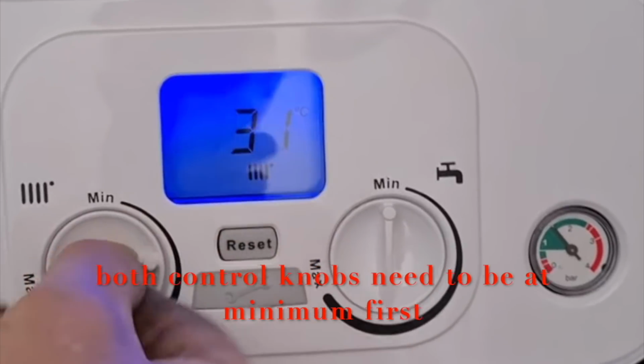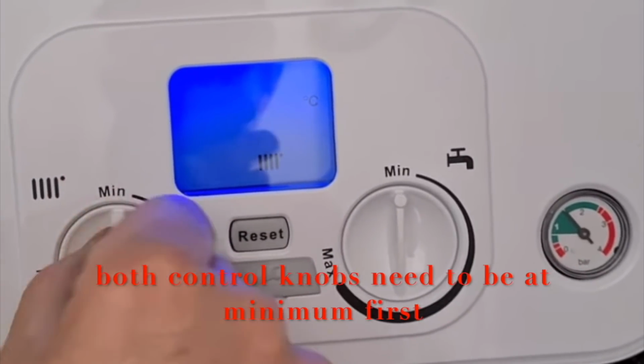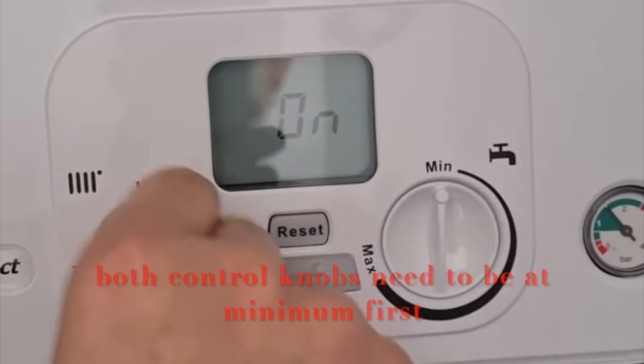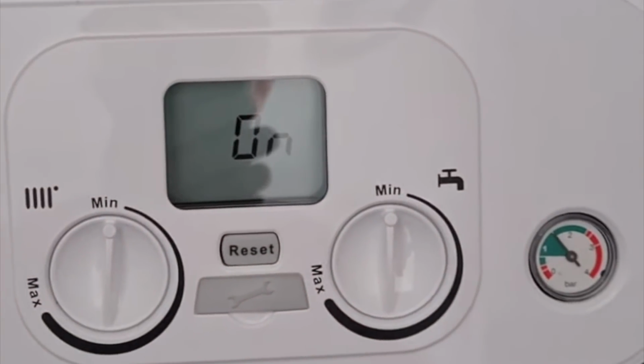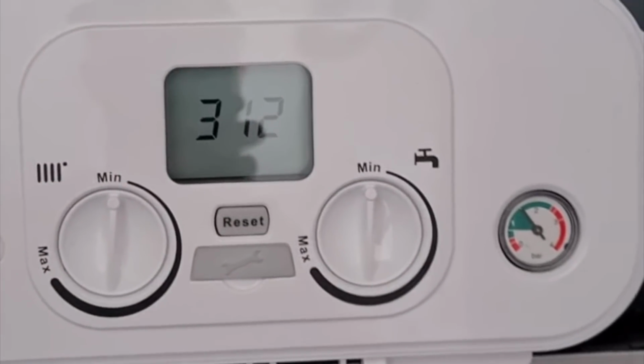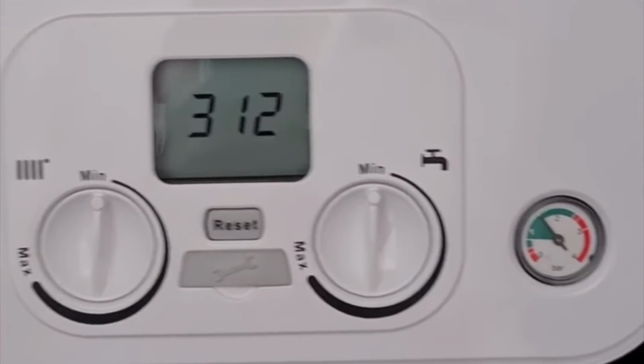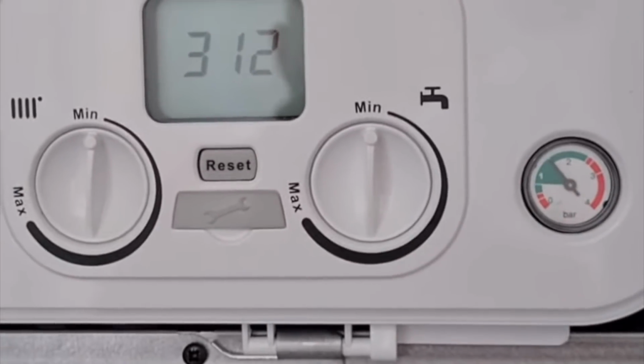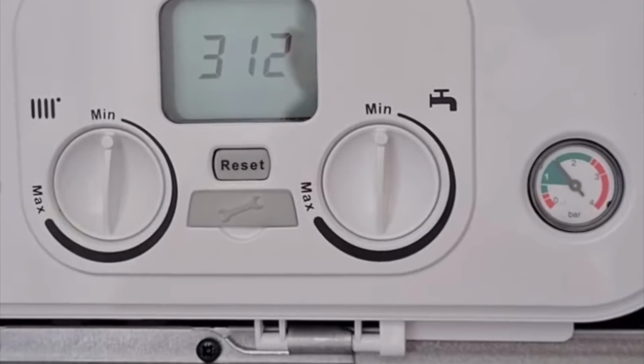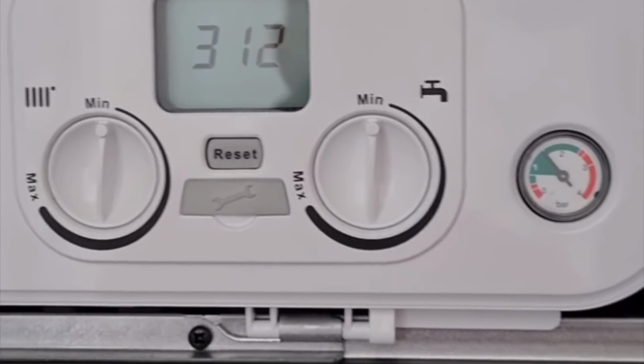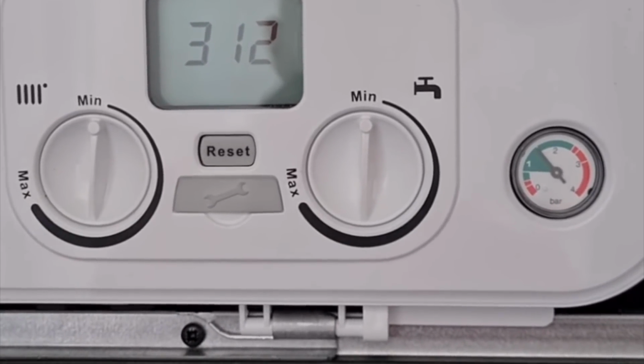Now, to first turn this boiler on, you need to put the central heating knob into minimum and then do 2 quick quarter turns, and this will then put the boiler on and put it in deaeration mode with a code of 312. Now this will be in deaeration mode for 5 or 6 minutes, so after this time has passed, you will then be able to commission the boiler.